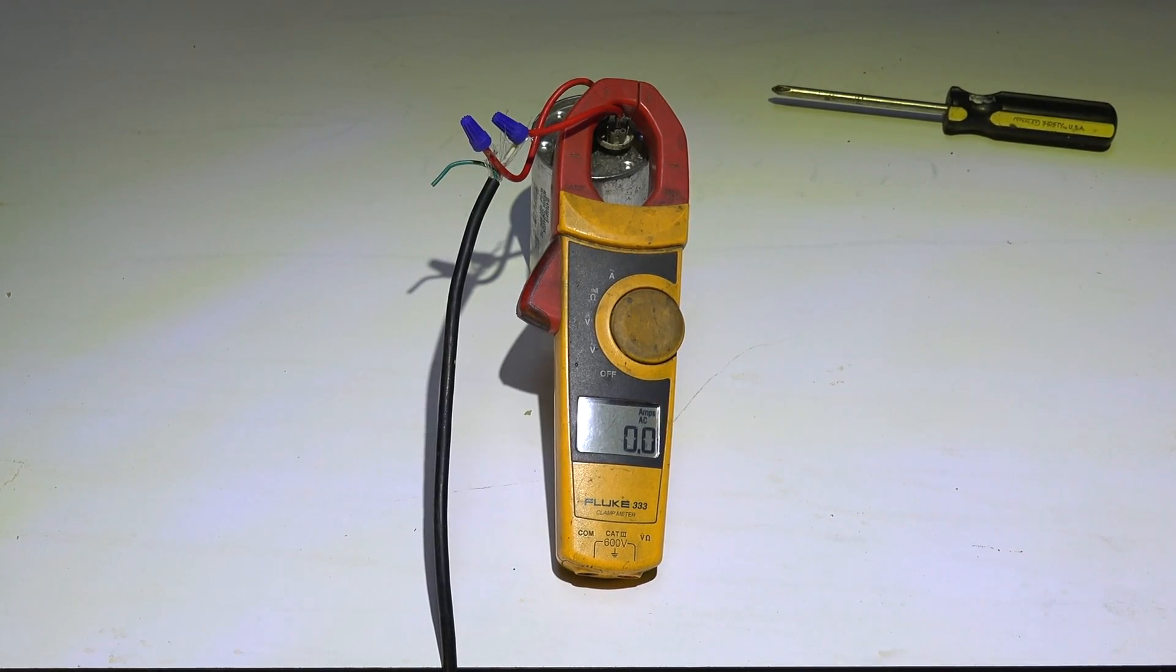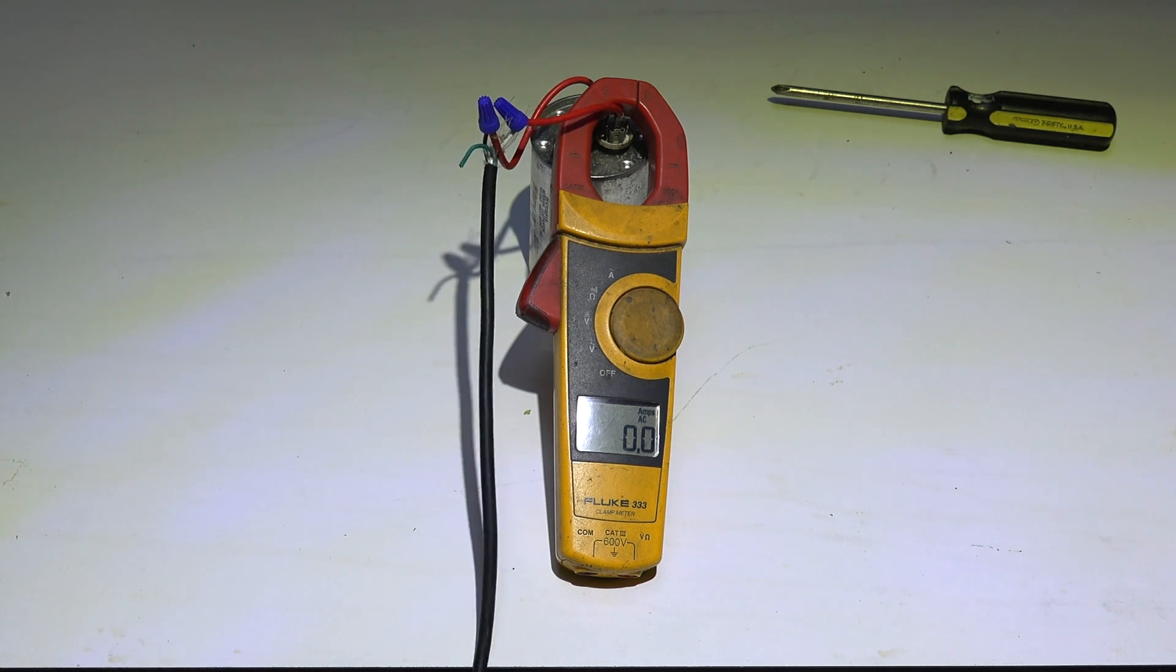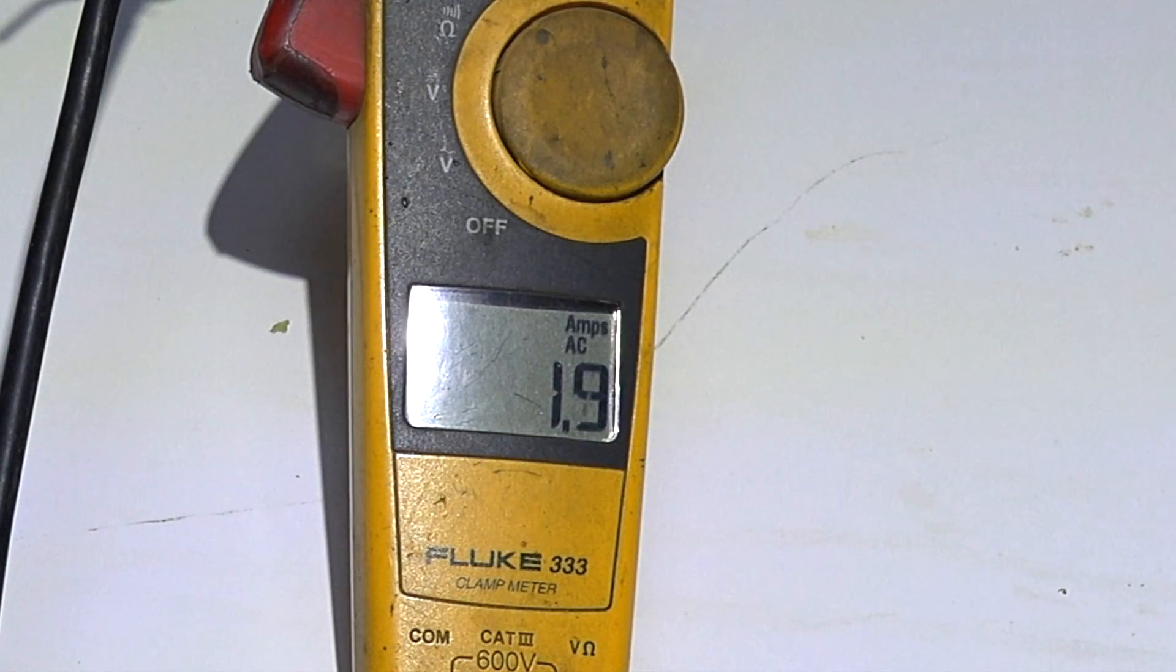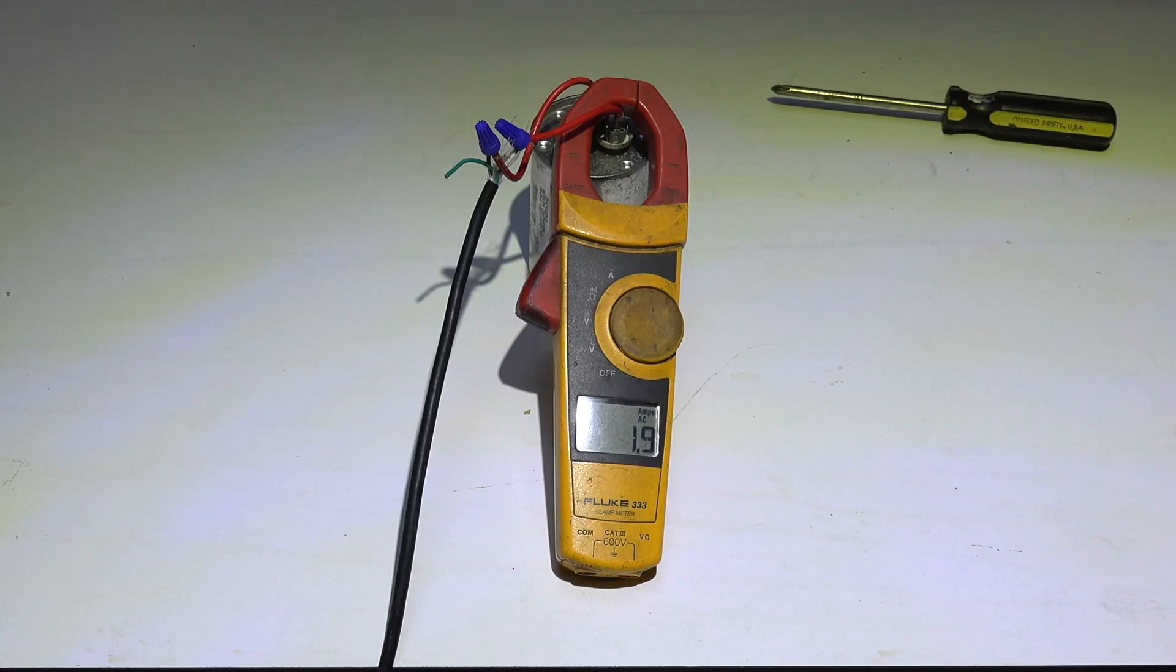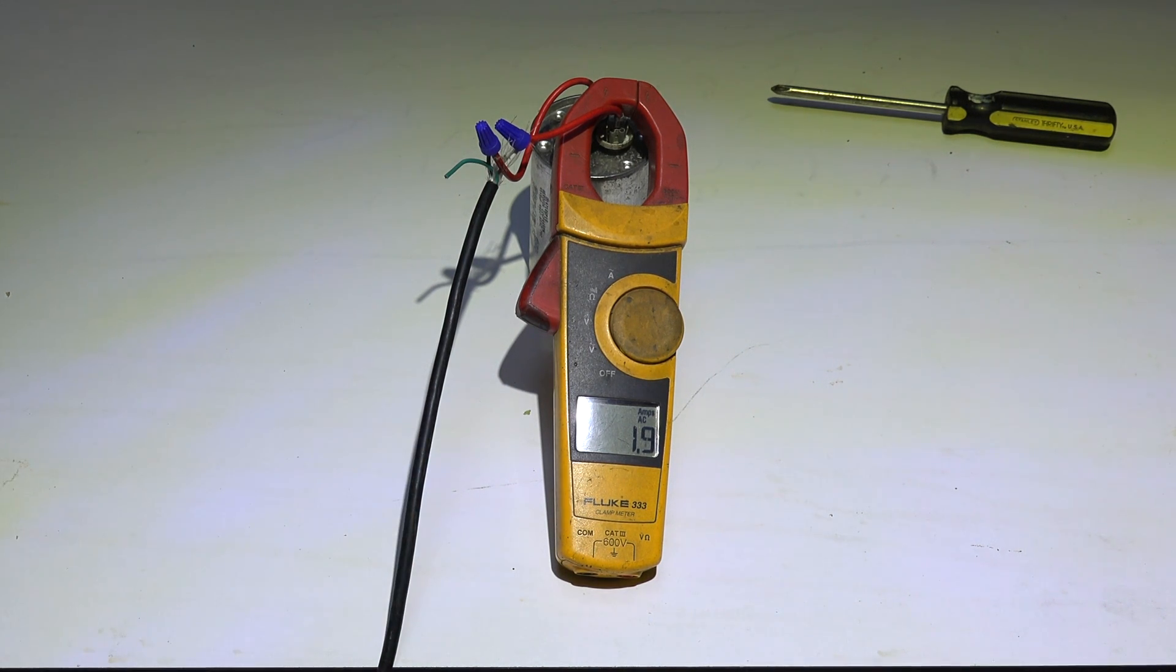Now I've got this set up on the 45 microfarad. And let's see what it draws now. Okay, we're drawing 1.9 amps. That would be a bit much for a crankcase heater. The one tenth of an amp might be a little bit low, but 1.9 would be excessive for the amp draw for a crankcase heater.